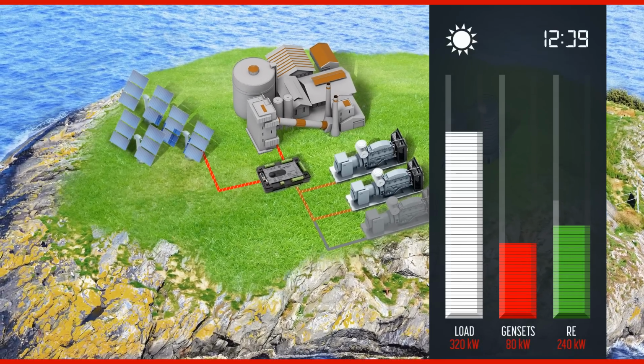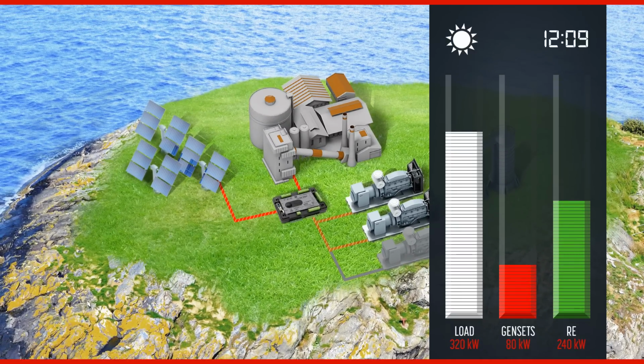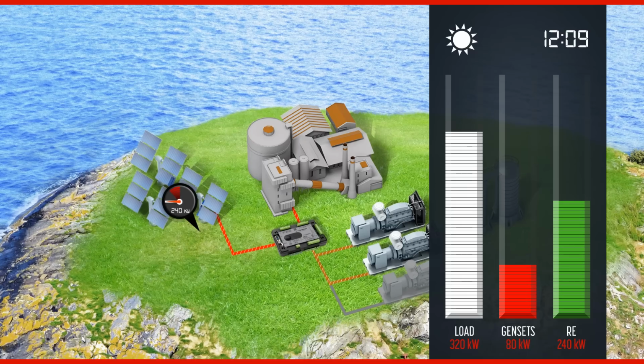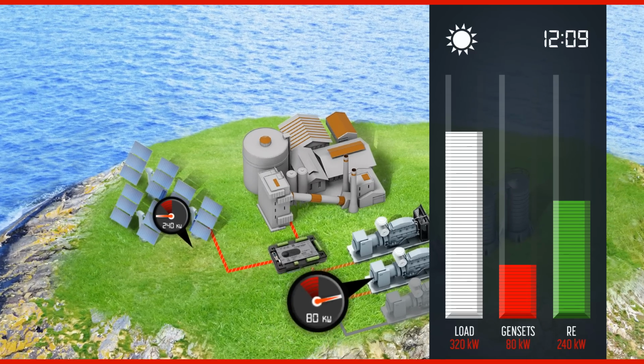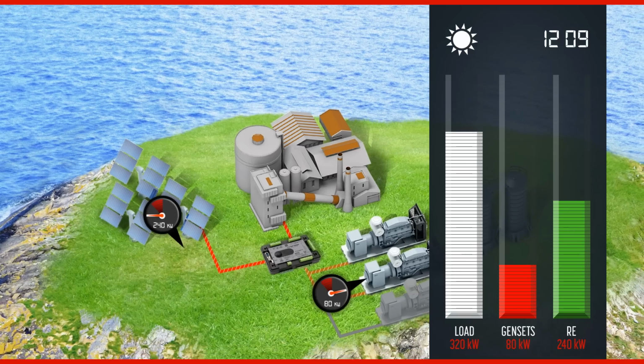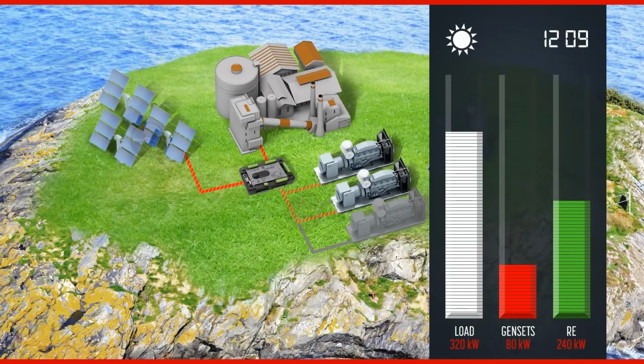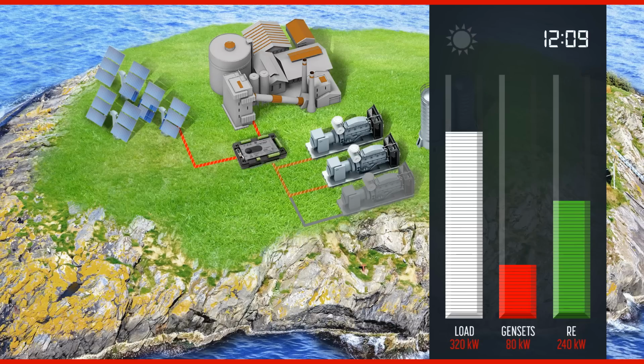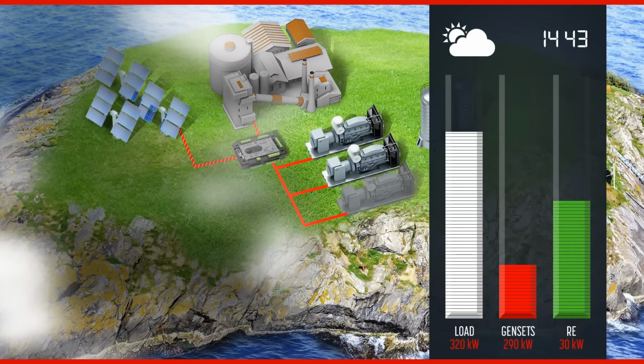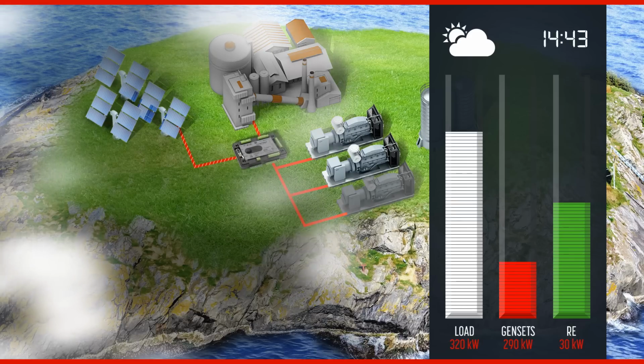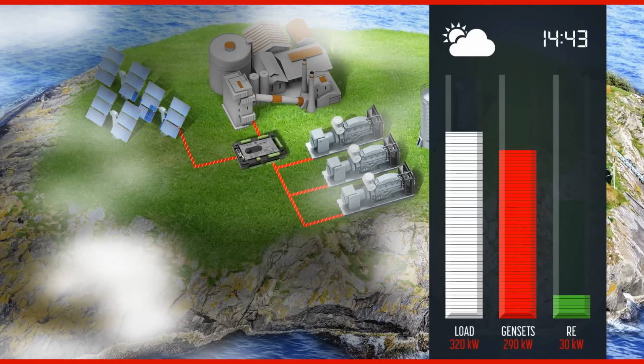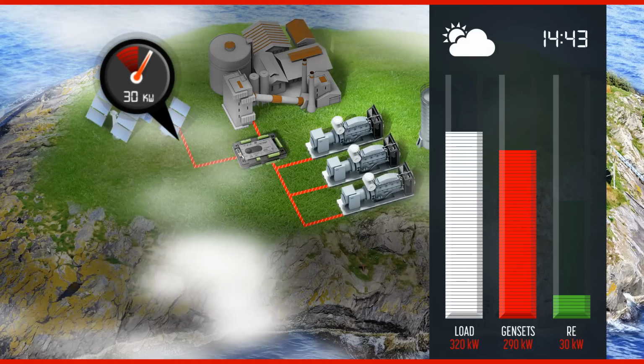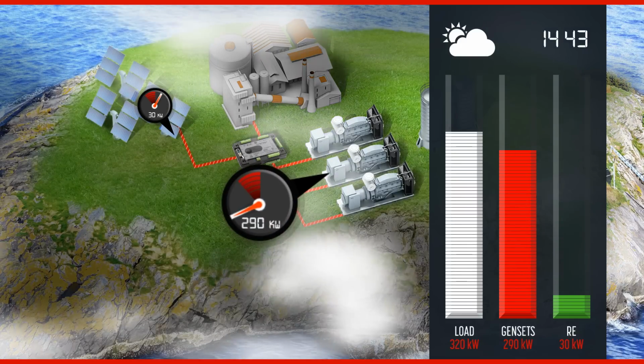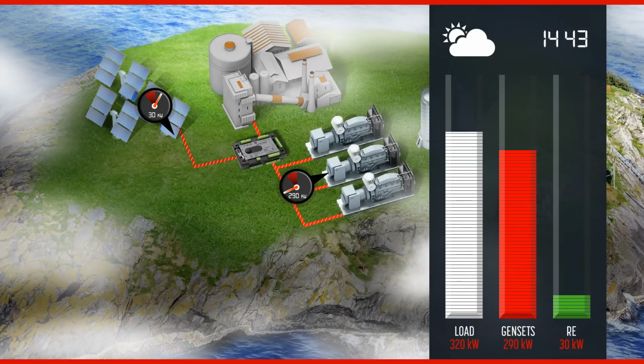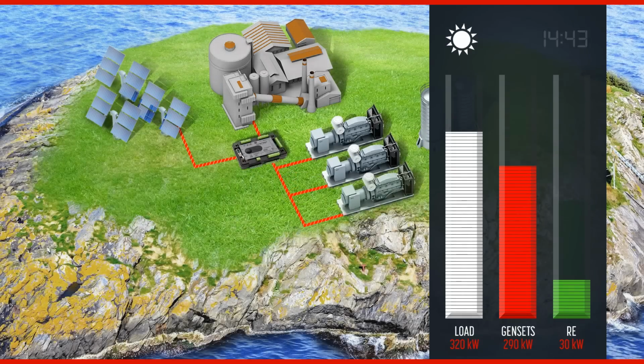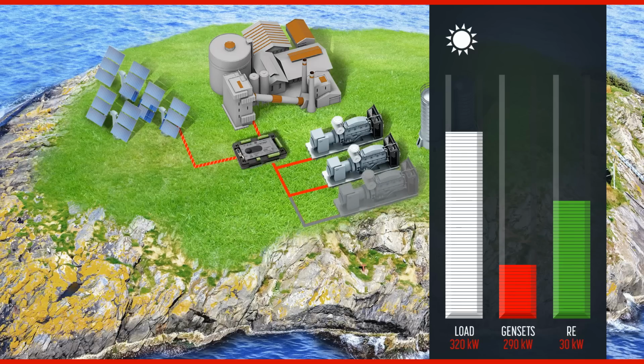In this case, the gensets run underloaded. In standard power management, the genset would be stopped, but in this case, this would reduce the reliability of the whole system. The input of the PV setup to the system must be reduced in order to protect the gensets from being underloaded. If the input from the PV array drops, such as in the case of cloud cover, the ComAp controller will automatically load the gensets to keep the power output smooth. When the input from the PV array becomes viable again, the controller will reduce the genset output to utilize as much power from the PV array as possible.